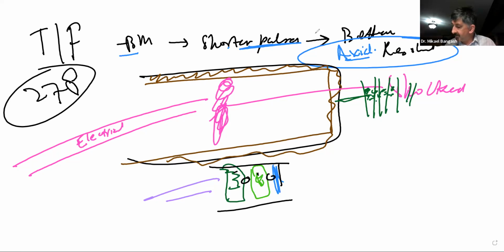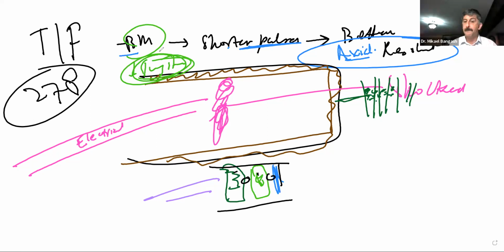Now, which component of an ultrasound transducer is made up of a slab of epoxy embedded with tungsten particles? That's your backing material. Okay, that's your backing material that is made up of tungsten, which is mainly just another element. Where will you find that element? Well, you'll find that element on your, what do they call it, periodic table. And this is, you can say, a harmful material. So ideally, people should not be directly exposed to that.